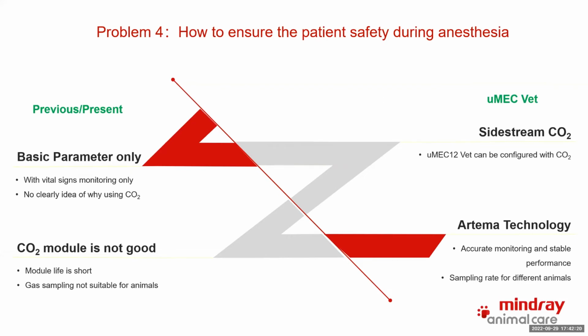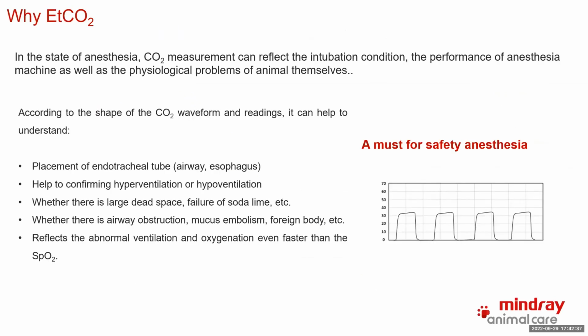And this Artema module can provide different sampling rates according to different animals. For large and small sizes, we provide different sampling rates and different accessories to be used, so it also makes sure of the accuracy of the CO2 readings. So for the CO2 parameter, as I mentioned, some doctors may not have a very clear idea why we should use the CO2. But actually the CO2 can reflect the intubation condition of the patient and also sometimes the performance of the anesthesia machine, as well as the physiological problems of the animals themselves.